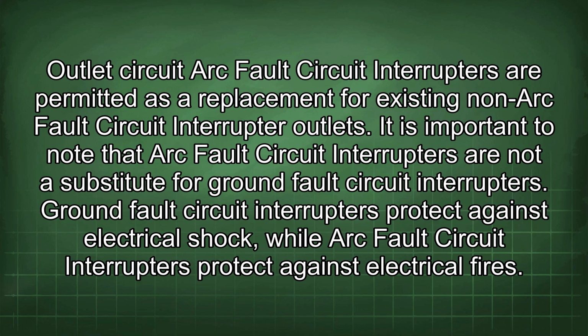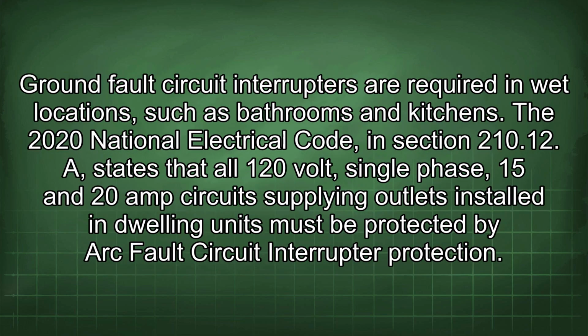It is important to note that arc fault circuit interrupters are not a substitute for ground fault circuit interrupters. Ground fault circuit interrupters protect against electrical shock, while arc fault circuit interrupters protect against electrical fires. Ground fault circuit interrupters are required in wet locations such as bathrooms and kitchens.